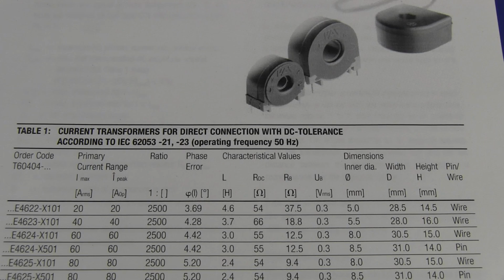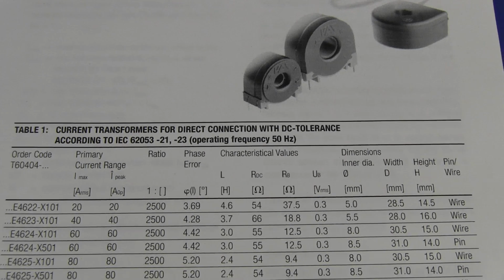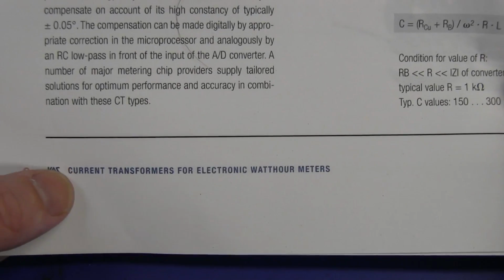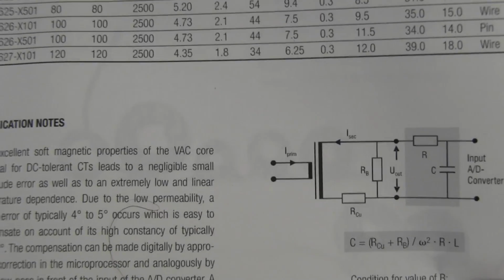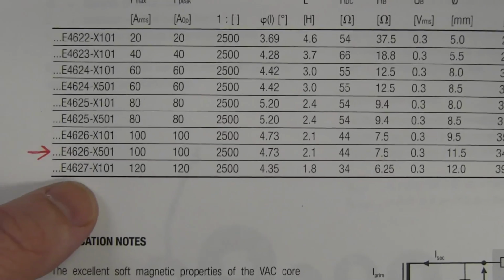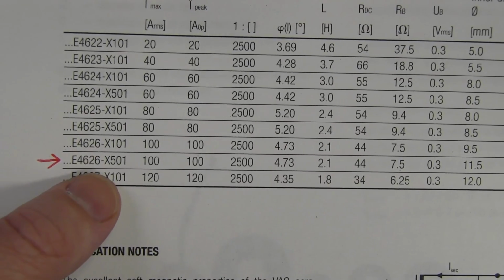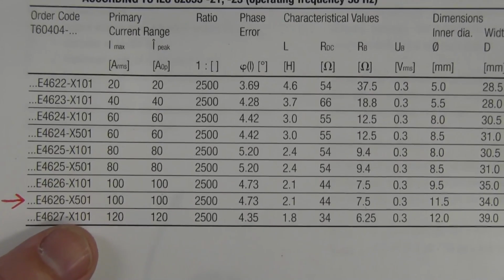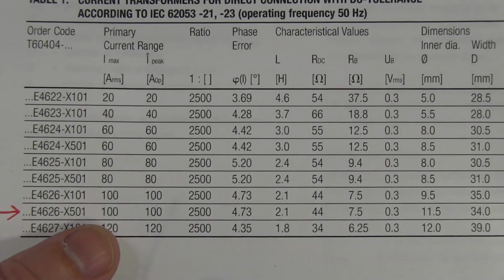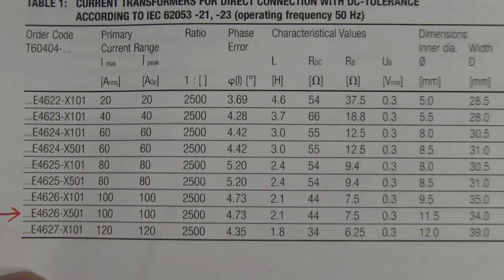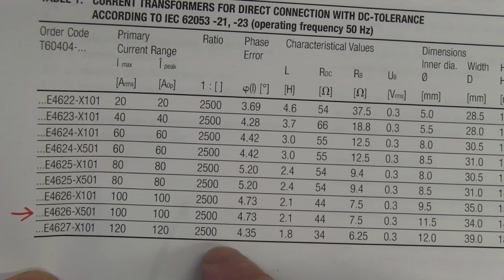Let's take a look at the current transformer we've got in here. It's a VAC brand, and they make current transformers specifically for electronic watt-hour meters. There it is down there, for electronic watt-hour meters. Brilliant, I like it. The one we've got here is the E4626X501. That's 100 amps primary current capability, with a current ratio of 2500.